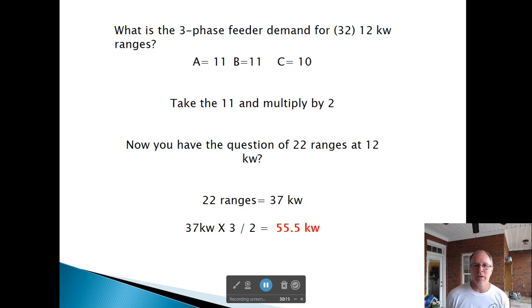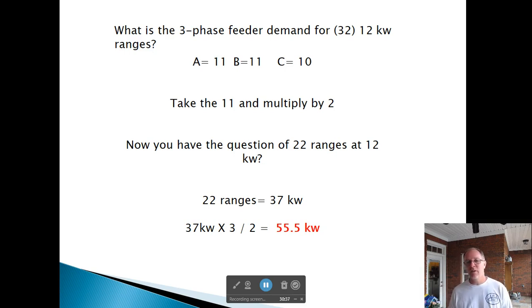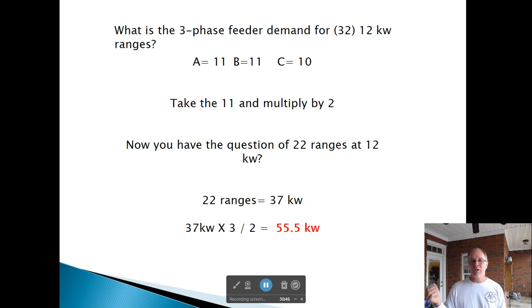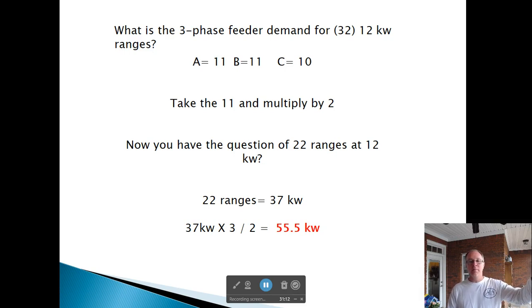What is the three-phase feeder demand for 32, 12 kW ranges? Divide equally: Phase A gets 11, Phase B gets 11, Phase C gets 10. The largest is 11 — multiply by 2 to get 22 ranges at 12 kW. Column C for 22 appliances is 37 kW. Multiply by 3 and divide by 2: 37 times 1.5 equals 55.5 kW.